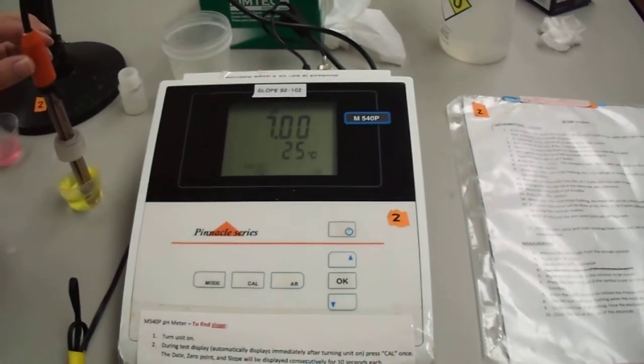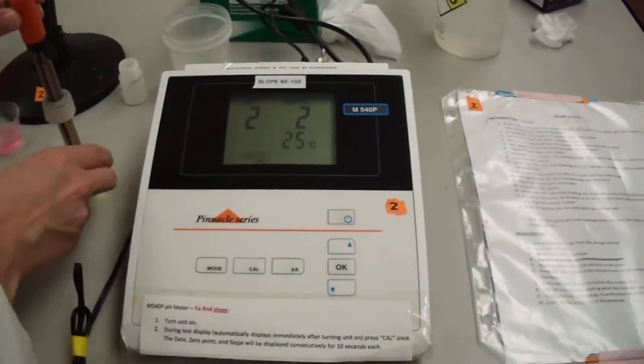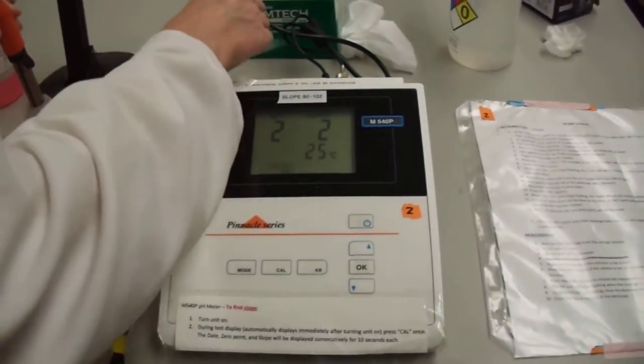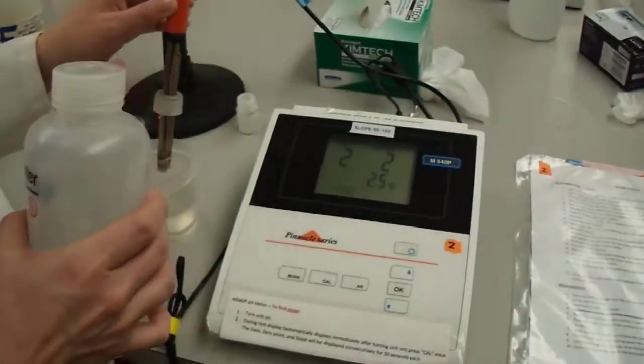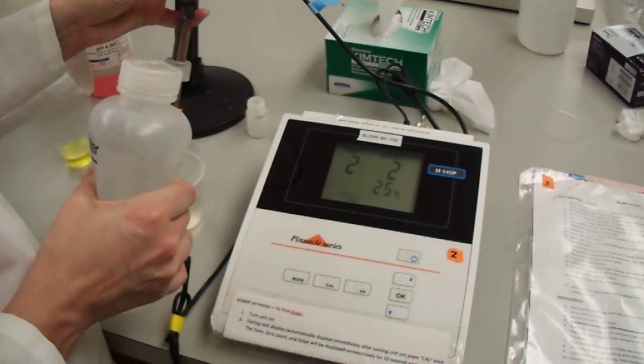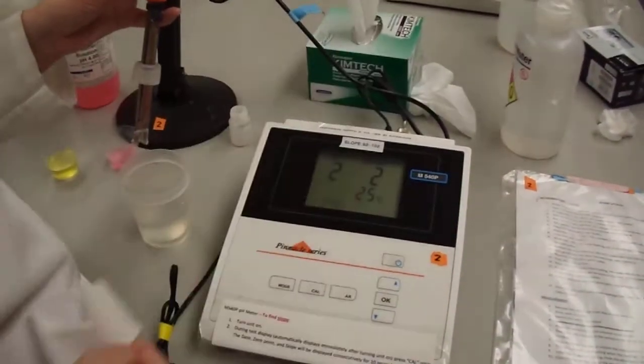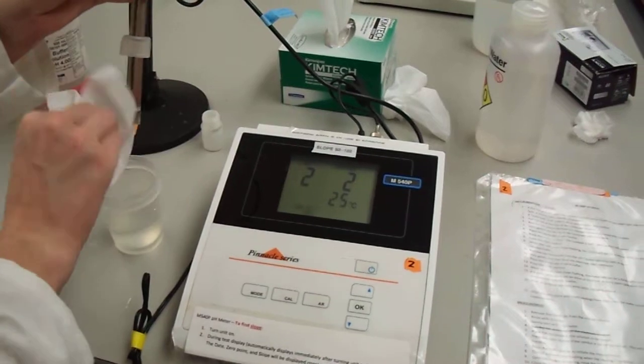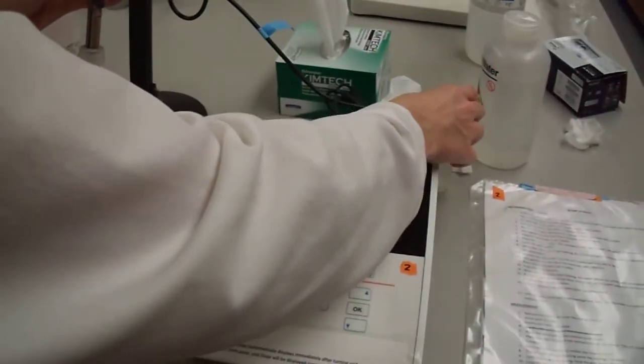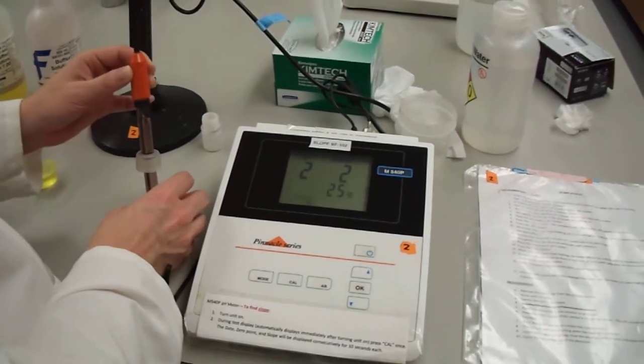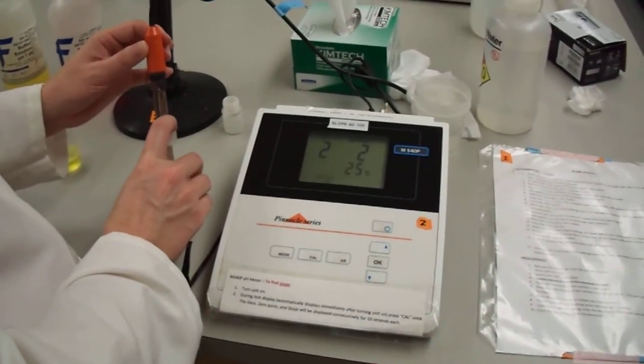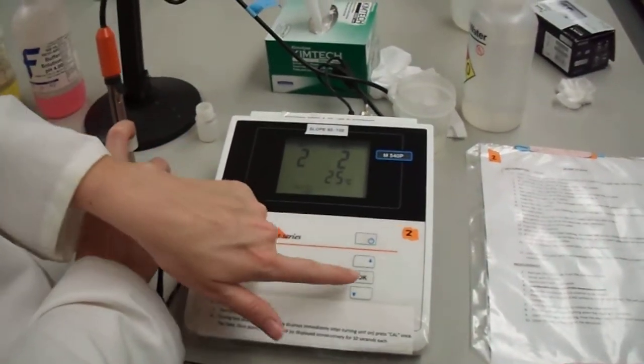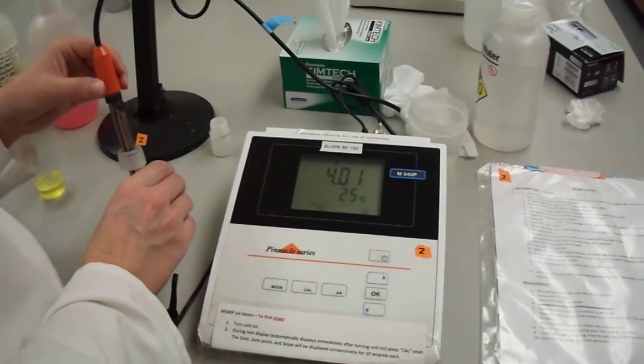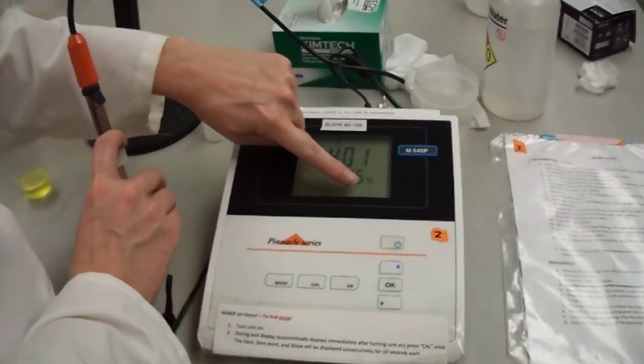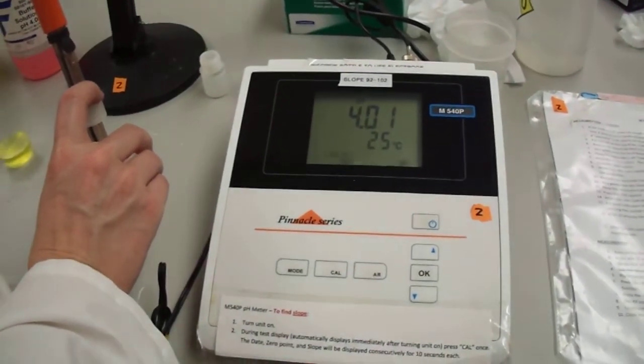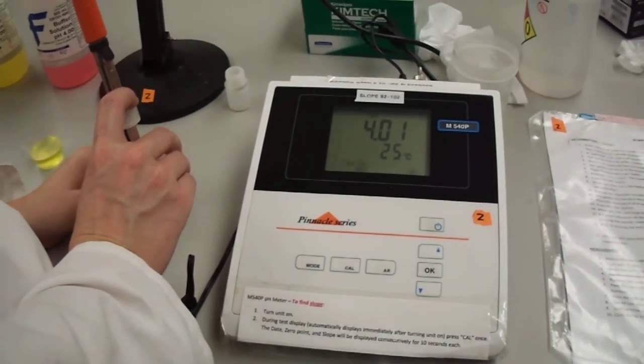As you can see, this may take a minute or two. Now you're going to remove the electrode from the pH 7 buffer and rinse with DI water. And like before, gently blot the tip of the electrode with a Kim wipe. Then place the electrode in the pH 4 buffer. Press the OK button. When the AR icon stops flashing, the meter will ask for a third buffer, which in this case we're only doing 2, so that will be our last one.